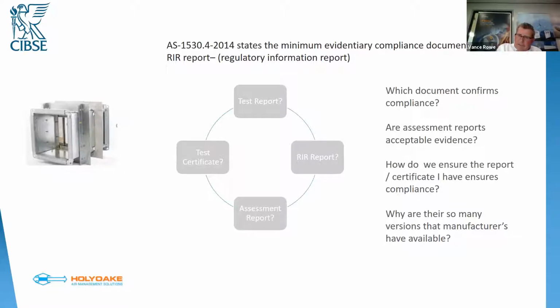But it does take a great number of those test reports to produce an assessment report. And we often end up in a situation with a certifier or a builder where they're insistent on seeing a test report. The few times that I've had a builder or a certifier in front of a test report, no disrespect to them, they haven't really understood what it is that they've read. If we go back to AS 1530.7, for example, a test report under AS 1530.7 gives you a series of results, but if you read those results, you don't know whether the damper has passed or failed at that point. You need to understand a little bit more of the picture to determine whether there's a pass or a failure on that particular product.